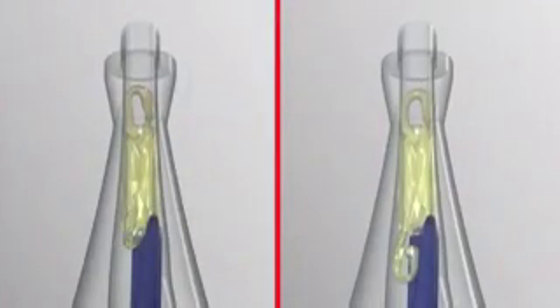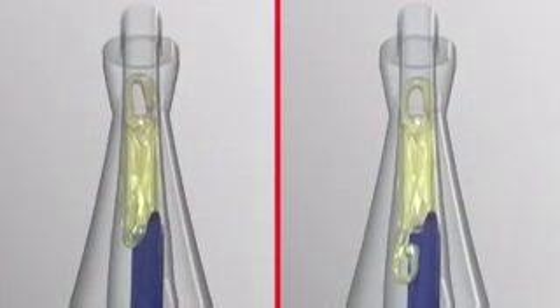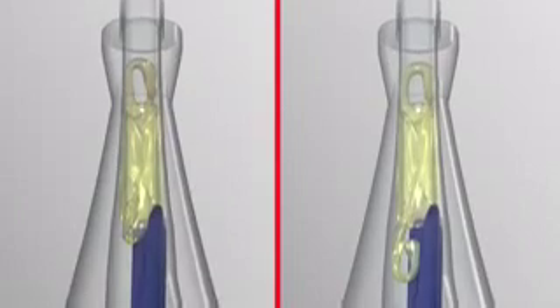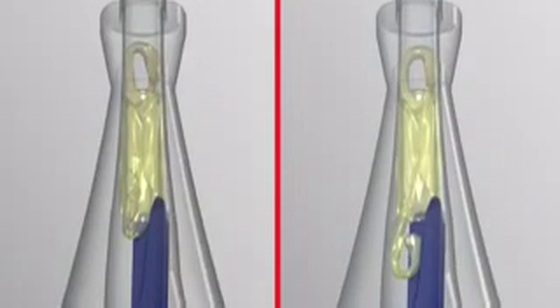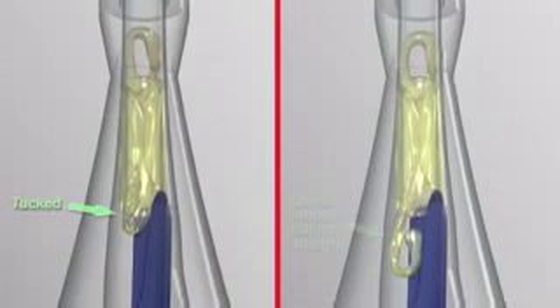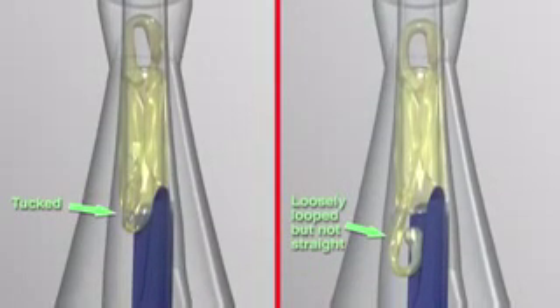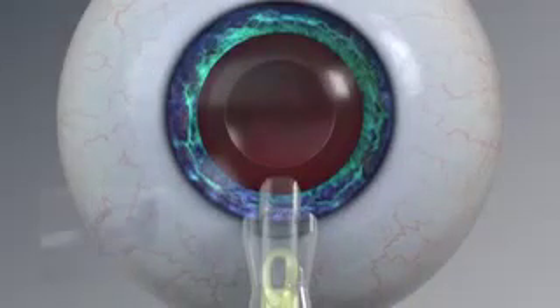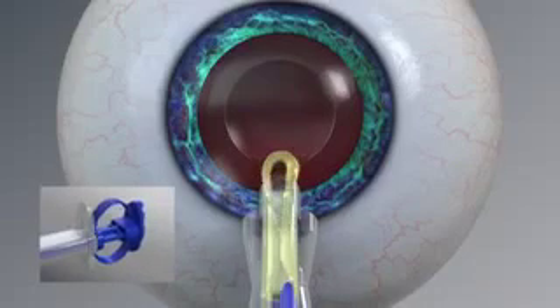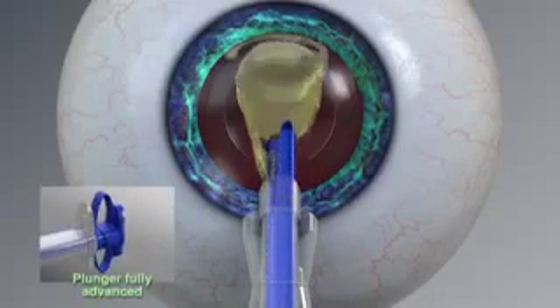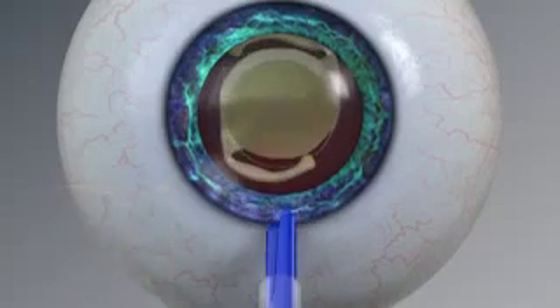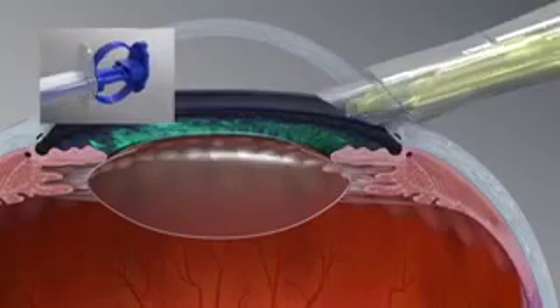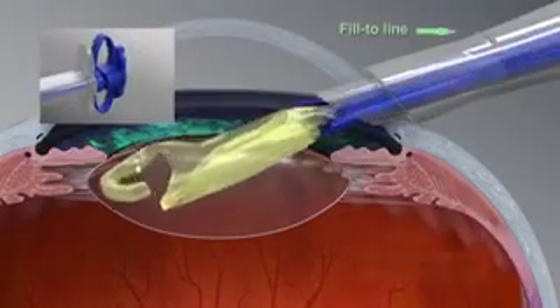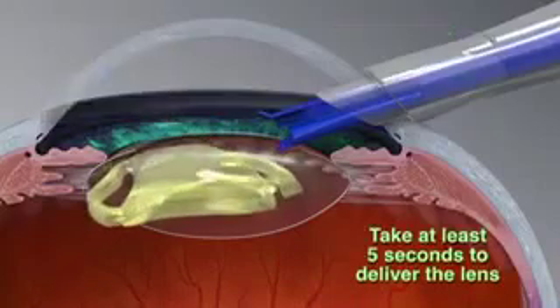In both images, the leading haptics are tucked, so no device rotation is required to place the lens into the capsular bag in the correct orientation. Notice the trailing haptic is either tucked or in a loosely looped but not straight configuration. In either case, with much of the trailing haptic alongside the plunger, this may require fully advancing the plunger in one smooth, continuous motion to ensure the entire trailing haptic clears the nozzle and the incision. Do not advance the plunger too fast, or lens damage may occur. It is recommended that delivery of the lens from the fill-to line should take at least 5 seconds.